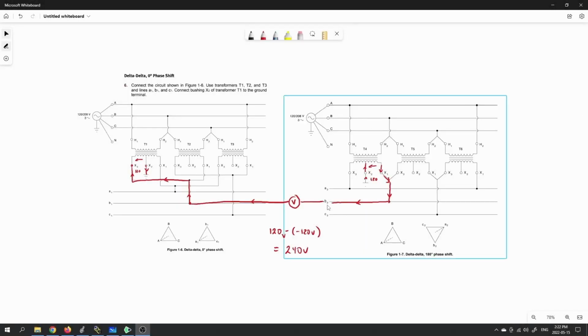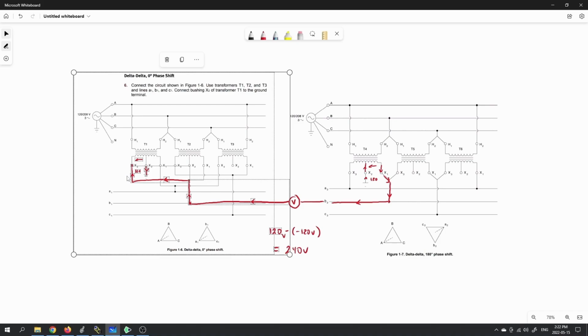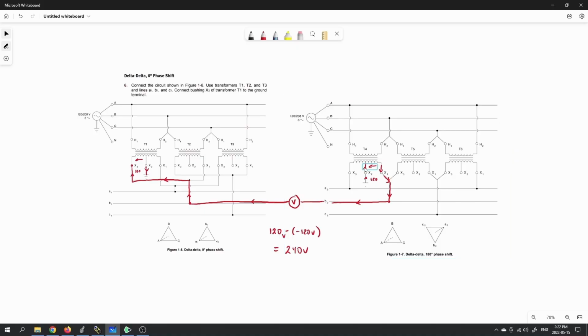The voltages we found from B1 to B2 were 240. Following the same thought process, I went from the voltmeter over here, which connects up to this point, then through picking up 120 volts, then to the ground connection of T1. From that ground connection on T1, coming over here picks up another 120, but in the opposite direction, then back to the source. So 120 volts minus negative 120 gives us 240 volts between B1 and B2, only going through one winding on T1 and one winding on T4.